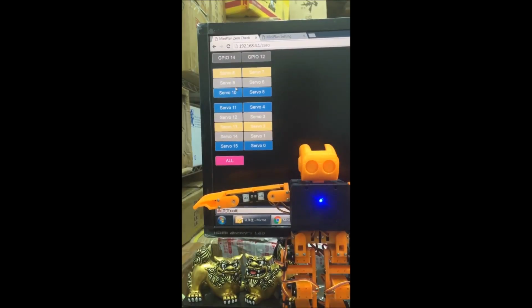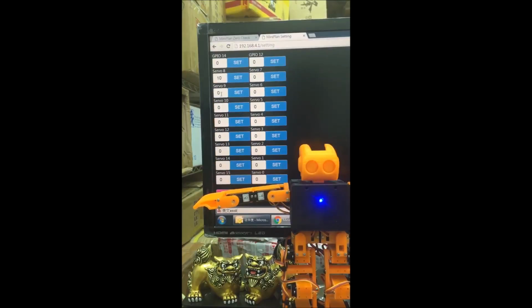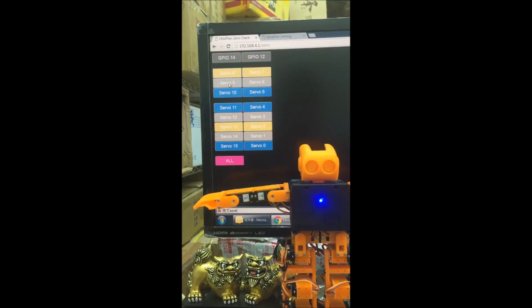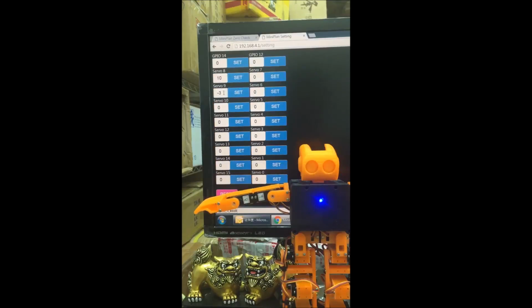Now the next thing we need to do is adjust servo 9. Same thing, I go back to the settings page, and on servo 9 I type in a negative value, maybe -3, and see where it goes. I press set and go back to the 0 page and press 9 again. I see I need my arm to tilt up, but the value -3 actually made it tilt down, so I need to adjust it back to the positive side of the numbers.